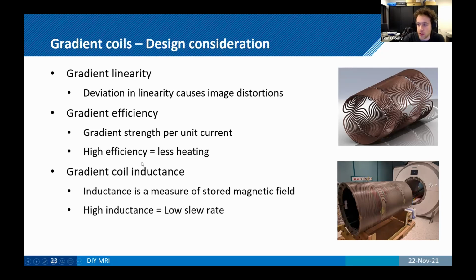And then gradient coil inductance. So inductance is a measure of how much magnetic field you're storing, which means that when you're slewing your gradients, changing your gradient strength, if you have a high inductance, it means that you can change those gradient strengths more slowly. The reason that it's a trade-off here, for instance, you can double the amount of wires that you're putting on your gradient cylinder, which is great because now you have double the gradient efficiency, but your inductance will be 4 times as high. So therefore it will take forever to slew your gradients. So when you're building these, work with the specifications of your gradient amplifier and decide on what are the trade-offs you're able to make there.